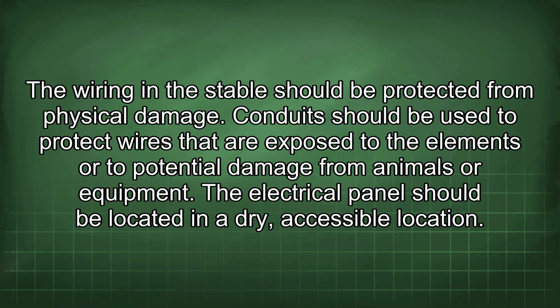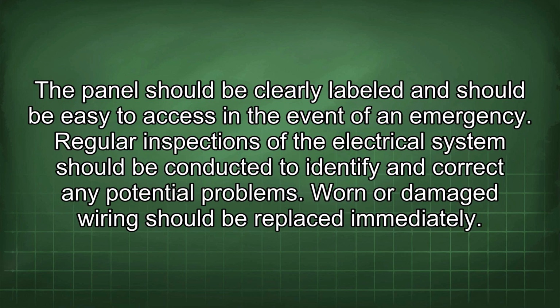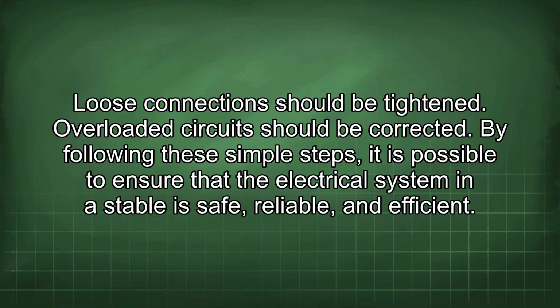The wiring in the stable should be protected from physical damage. Conduits should be used to protect wires that are exposed to the elements or to potential damage from animals or equipment. The electrical panel should be located in a dry, accessible location. The panel should be clearly labeled and should be easy to access in the event of an emergency. Regular inspections of the electrical system should be conducted to identify and correct any potential problems. Worn or damaged wiring should be replaced immediately. Loose connections should be tightened. Overloaded circuits should be corrected.